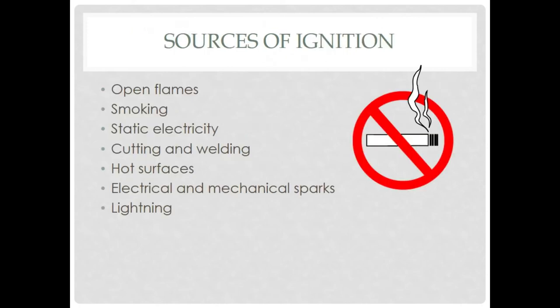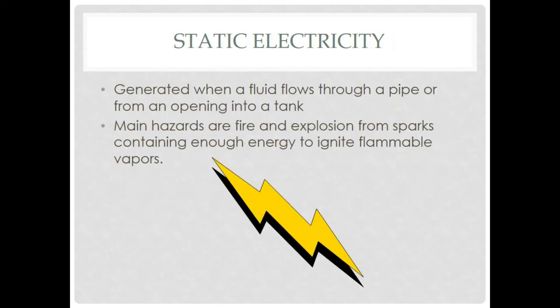Sources of ignition for flammable liquids include smoking, static charge, open flames, cutting, welding, grinding, hot surfaces, electrical or mechanical sparks, and lightning. A very significant ignition source is static electricity, which we will cover in a separate video. Static electricity is generated when a fluid flows through a pipe or from an opening into a tank. The main hazards are fire and explosion from sparks containing enough energy to ignite flammable vapors.